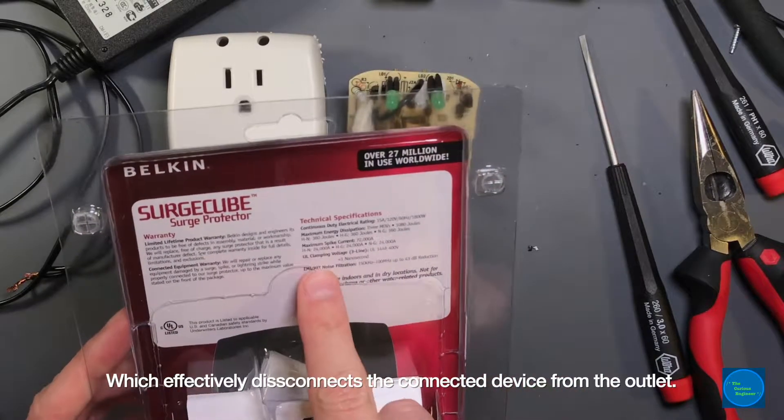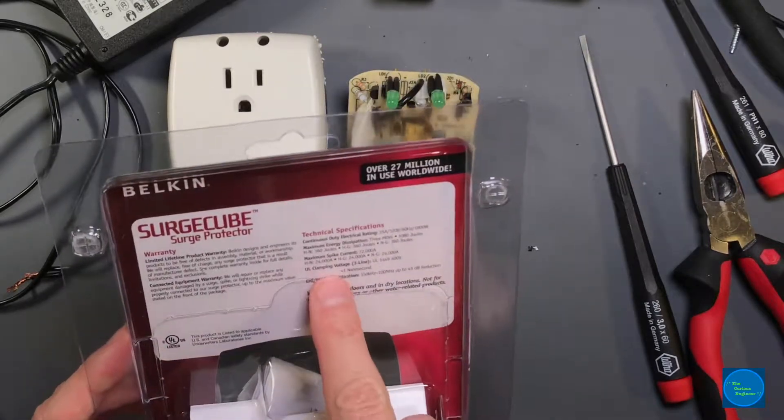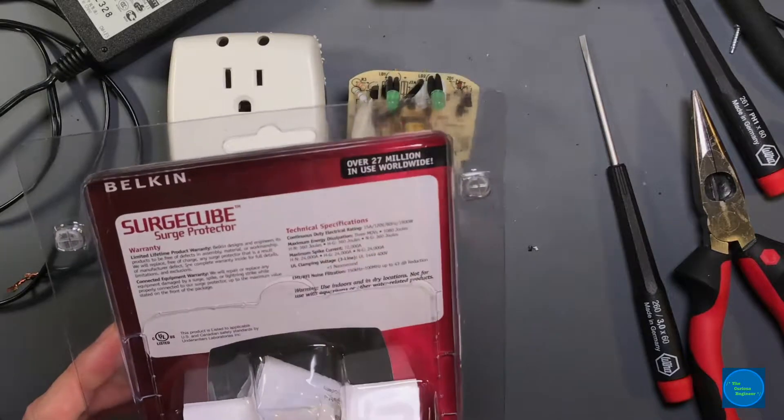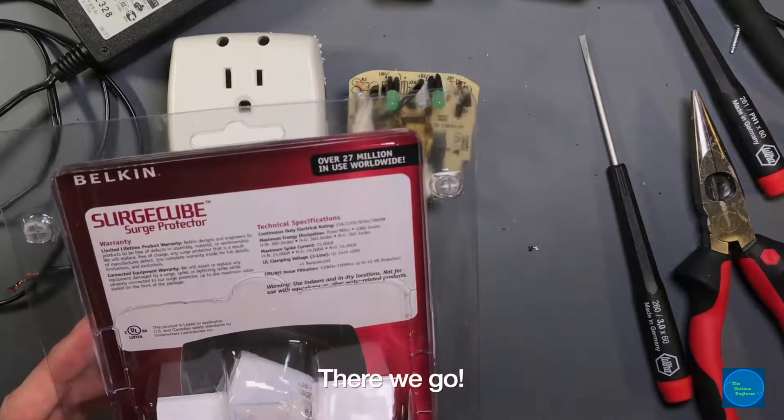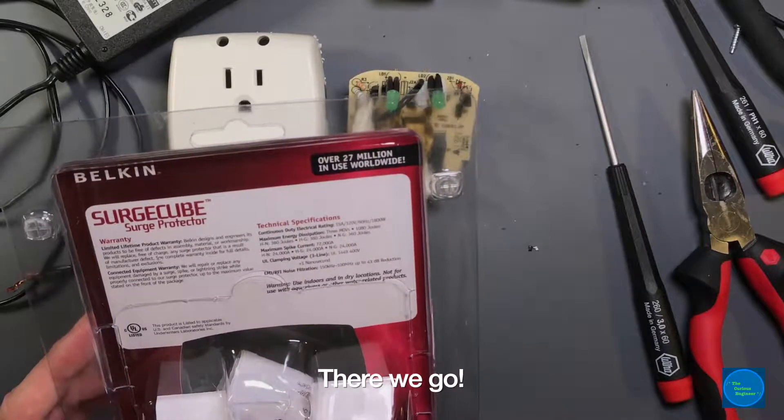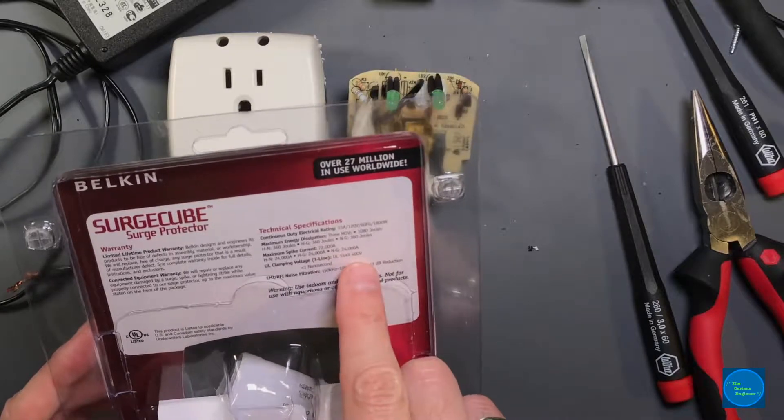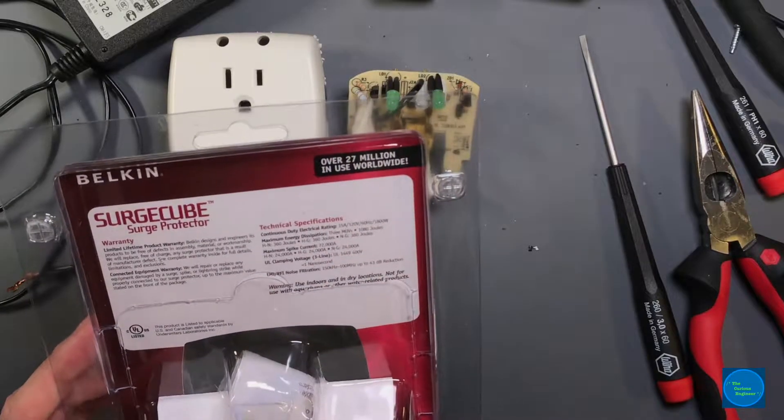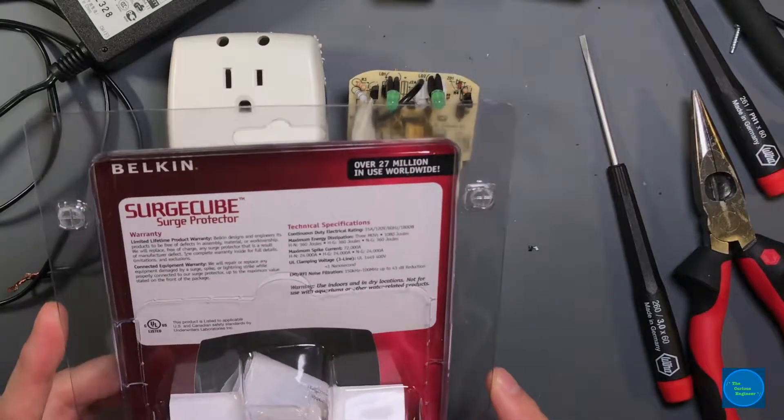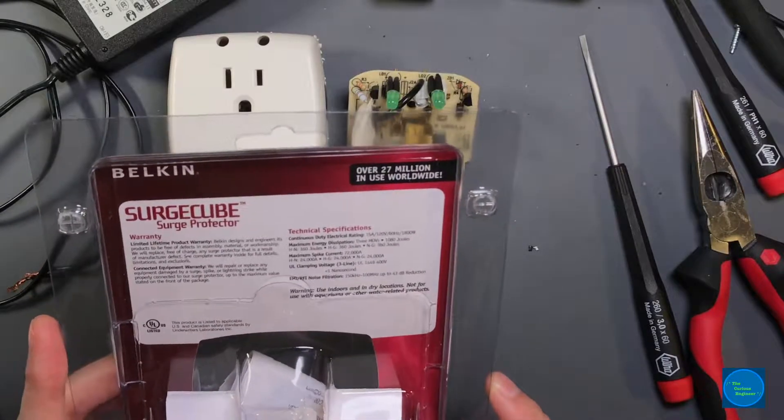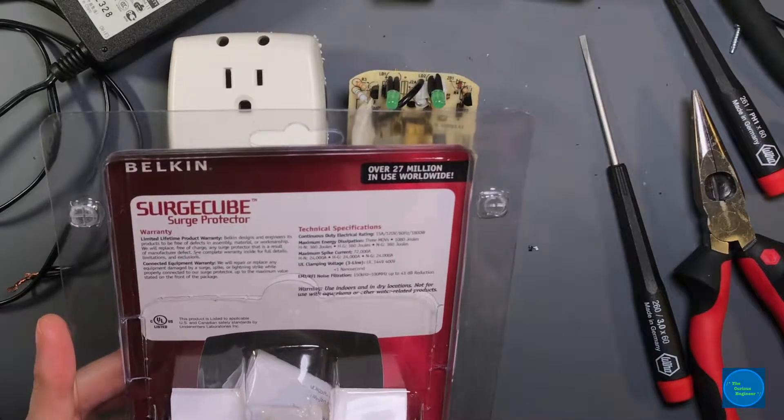I kind of jumped ahead a little bit. But then there's the UL clamping voltage. That's the voltage at which it will clamp down and shunt all the energy to wherever it's coming from, to either neutral or ground. That voltage per the UL 1449 standard is 400 volts, and that occurs within less than one nanosecond. Just bear that in mind, we'll come back to that in a moment.